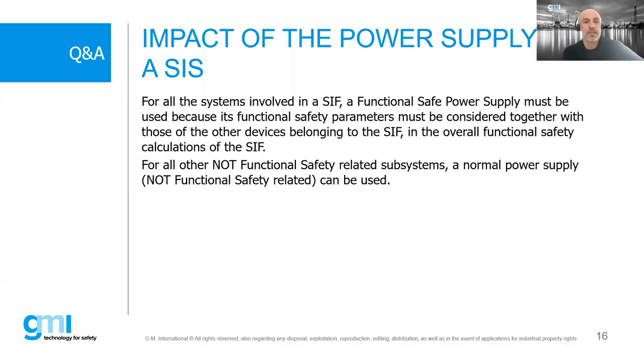This is, of course, the SIF. A safe power supply is a product that has been designed in a safe manner, with safety components and high quality components. And of course, besides everything, if a SIF is not required, a safe power supply is a good way to increase the safety and the availability of your system, because the failure rate of single components is calculated and put into the FMEDA of the device, and it grants more, if not safety, more availability. But it's not required, of course. You can use a safe power supply or not in a non-safety application.